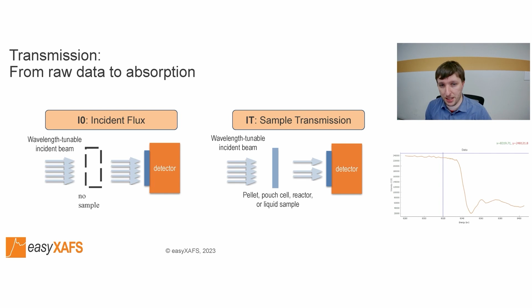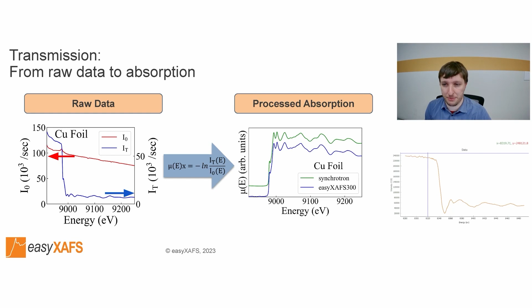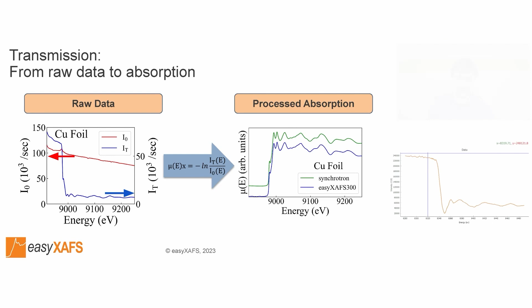Here we have an example of the I0 and IT data for the copper K edge of a copper reference foil. In contrast to the small changes in the I0 data, the IT measurement has a large drop in intensity resulting from the copper K edge absorption. We can then calculate the absorption spectra from the I0 and IT measurements using the natural log equation shown here. The resulting copper K edge absorption data for the laboratory instrument is compared to synchrotron measurements. The laboratory measurements achieve good synchrotron quality energy resolution.